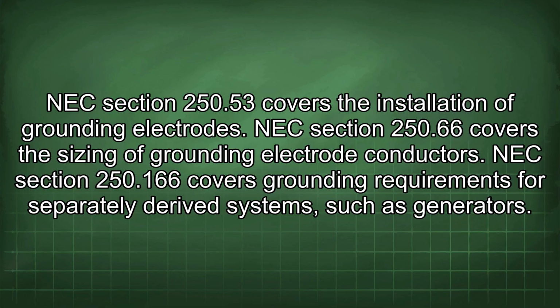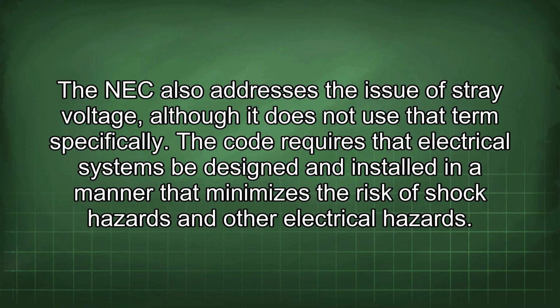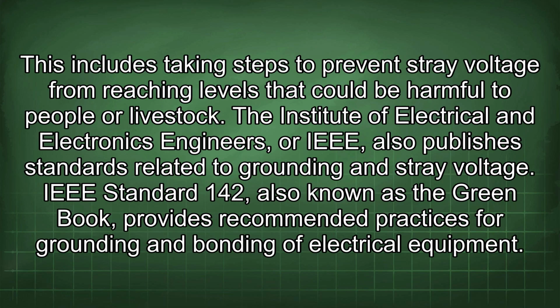NEC Section 250.66 covers the sizing of grounding electrode conductors. NEC Section 250.166 covers grounding requirements for separately derived systems such as generators. The NEC also addresses the issue of stray voltage, although it does not use that term specifically. The code requires that electrical systems be designed and installed in a manner that minimizes the risk of shock hazards and other electrical hazards. This includes taking steps to prevent stray voltage from reaching levels that could be harmful to people or livestock.